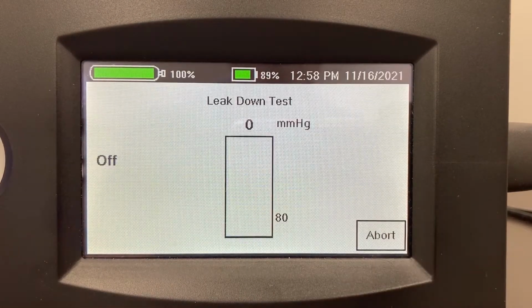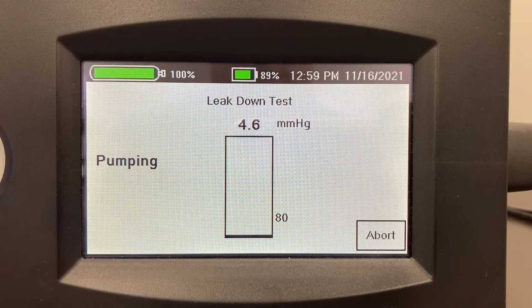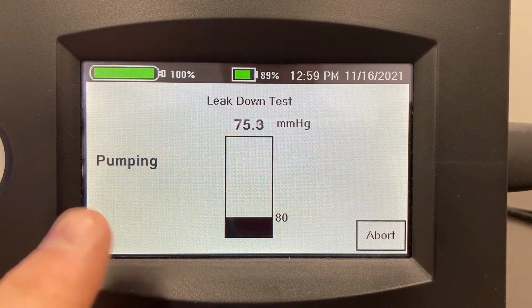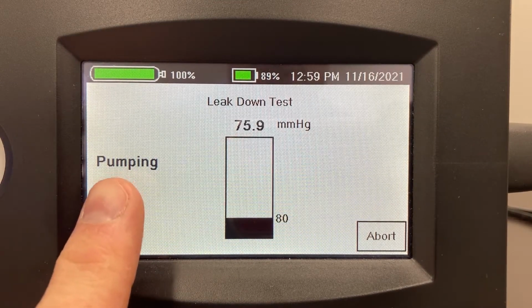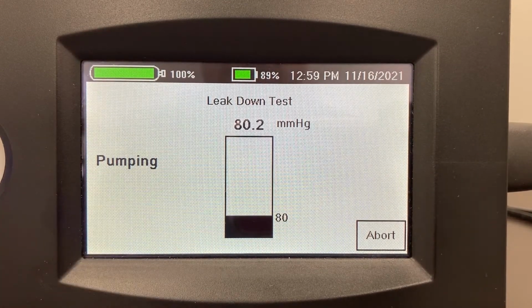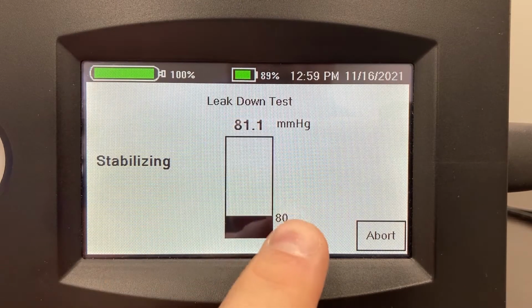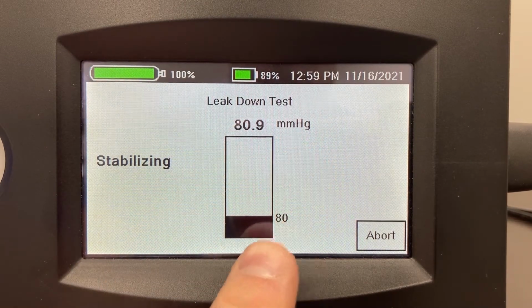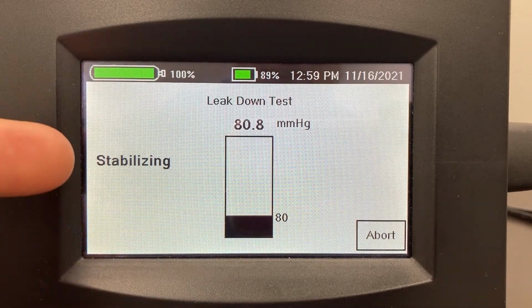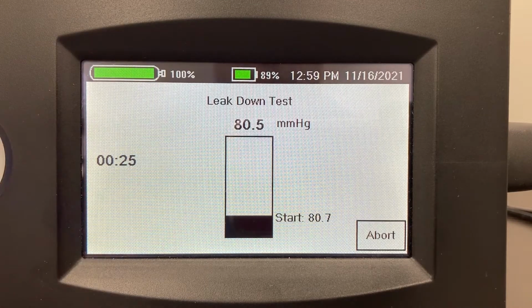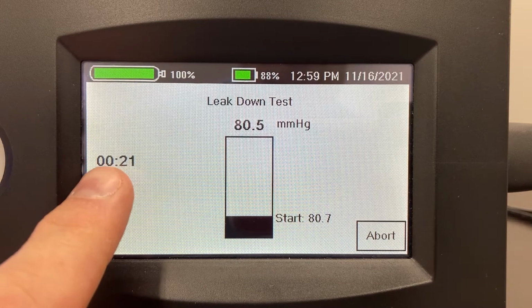Once we press start, we'll see the SmartTank is pumping up the module that's being tested up to pressure. After it's done pumping, it'll wait for the pressure to stabilize. We can see this is the actual pressure. This is the pressure it's targeting, 80 millimeters of mercury. Now it's stabilizing and waiting for the gas pressure to be stable. Now that the gas is stable, it started its countdown.